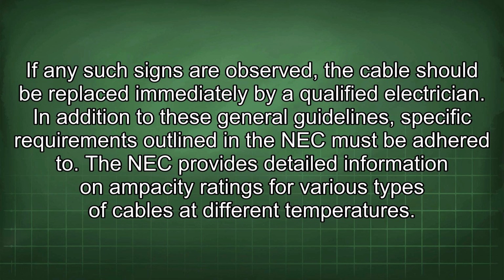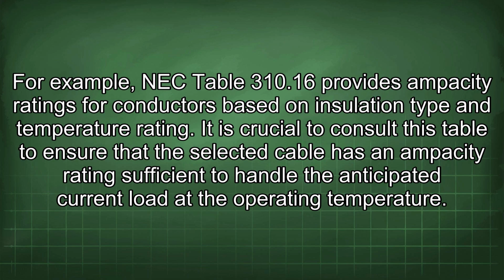In addition to these general guidelines, specific requirements outlined in the NEC must be adhered to. The NEC provides detailed information on ampacity ratings for various types of cables at different temperatures. For example, NEC Table 310.16 provides ampacity ratings for conductors based on insulation type and temperature rating. It is crucial to consult this table to ensure that the selected cable has an ampacity rating sufficient to handle the anticipated current load at the operating temperature.